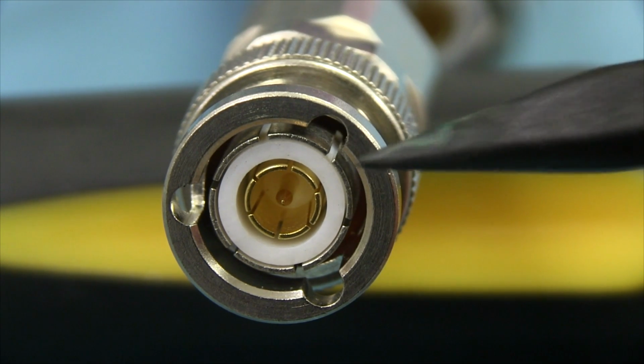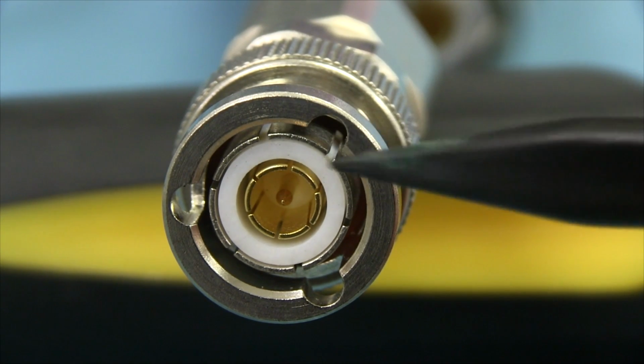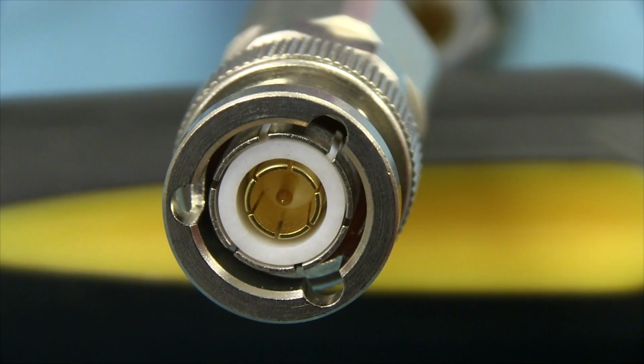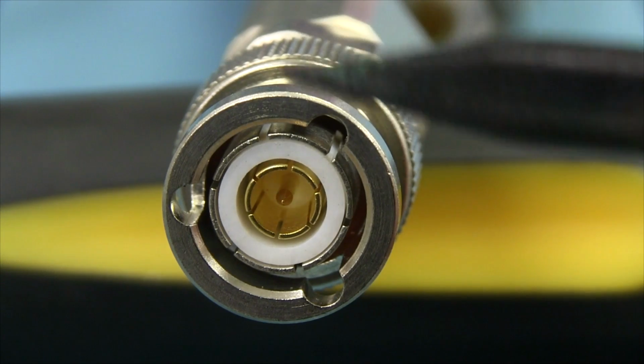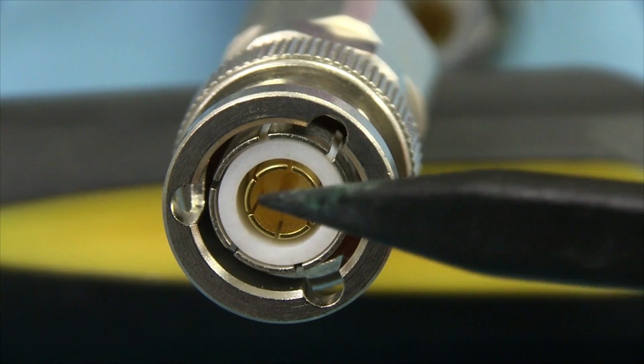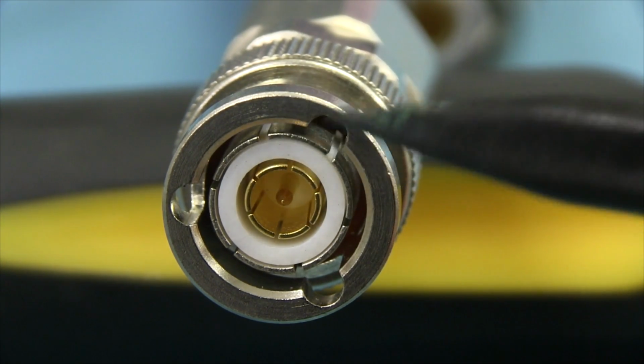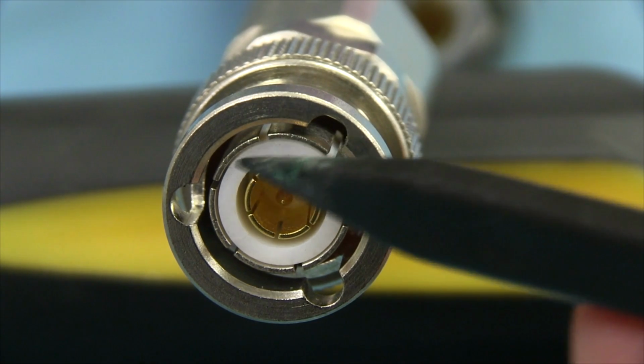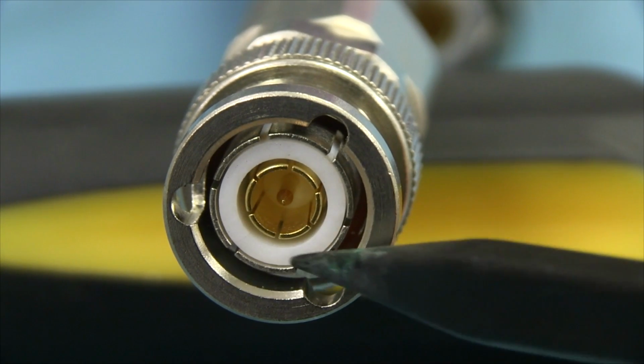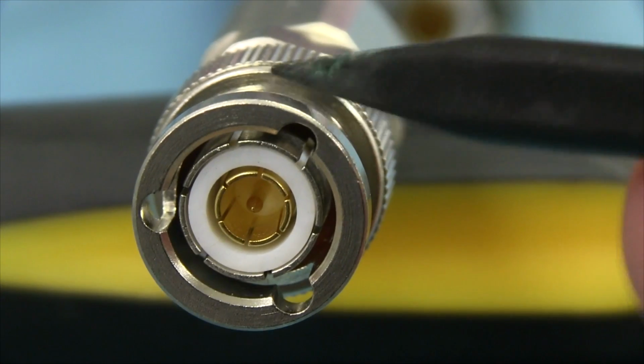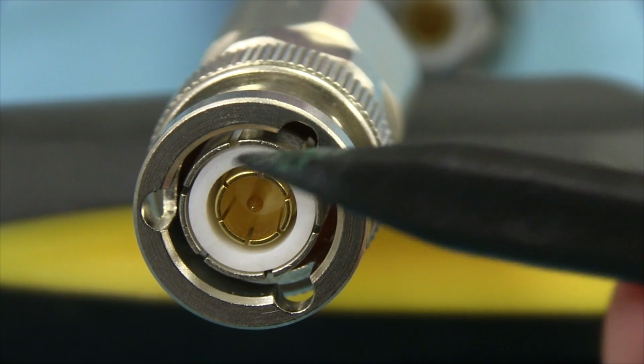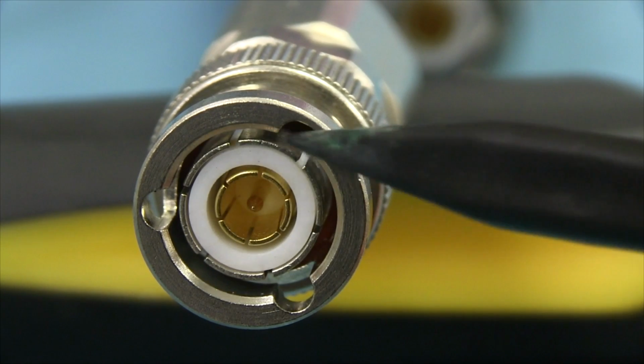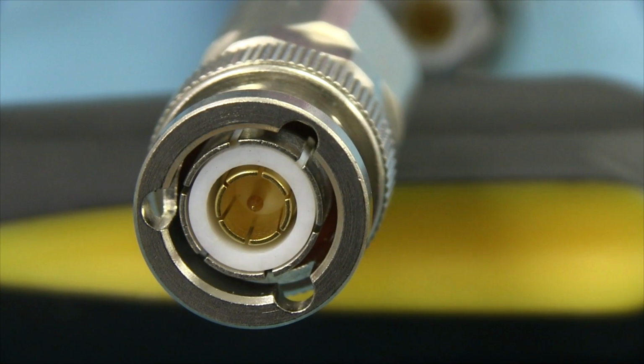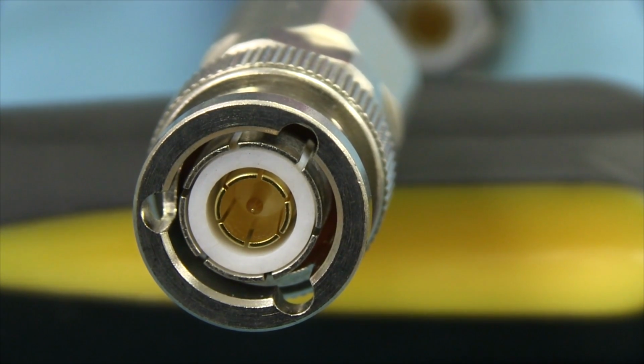But apart from that, not a huge amount else. Anything that needs real critical shielding, you're going to use these triaxial coaxes. It looks very similar to a regular coax. In fact, from the outside, without looking at the end here, you really have a hard time telling that it would be a triaxial type. So we've got the outer shield around here, which is of course connected through to your regular coax body here, and that's going to be connected to mains earth. So that one, physical mains earth ground.